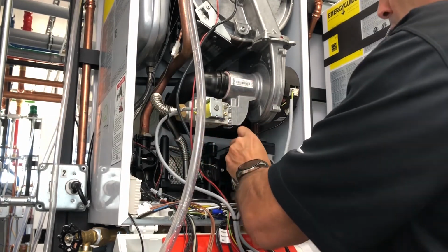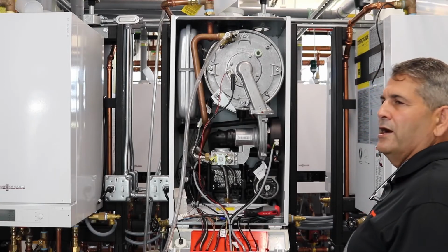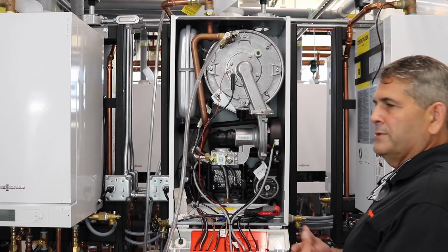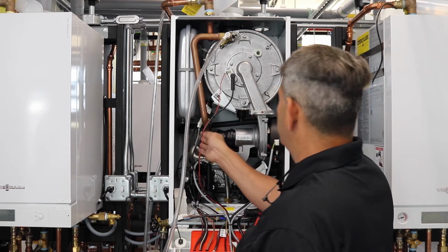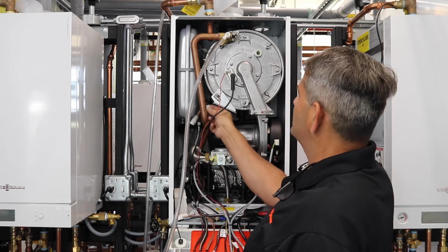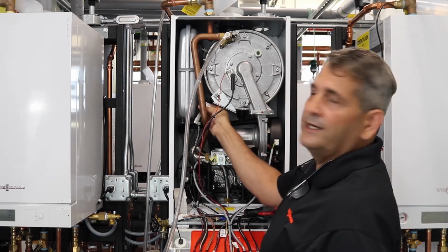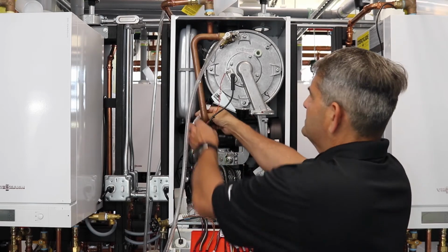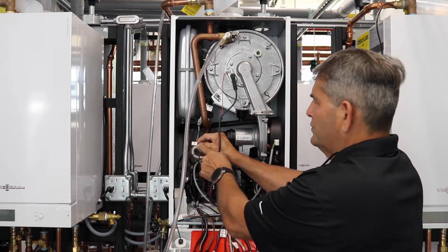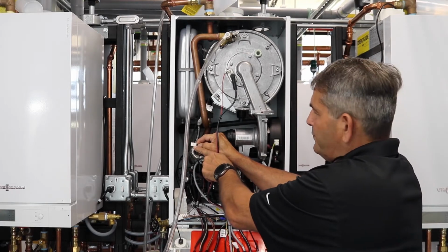Grab our little cup of water here. All right, so now we've got to locate our flow switch itself. What I normally did when I was in tech support was have the guys go to the 33 plug. So this is your 33 plug. As you can see, right on the thing it says 33 here. It's upside down, but it's there. And we have 33 on this plug here as well.